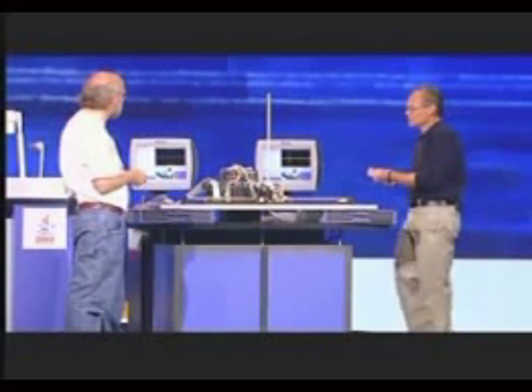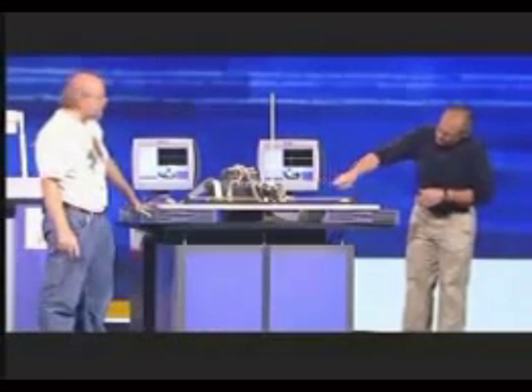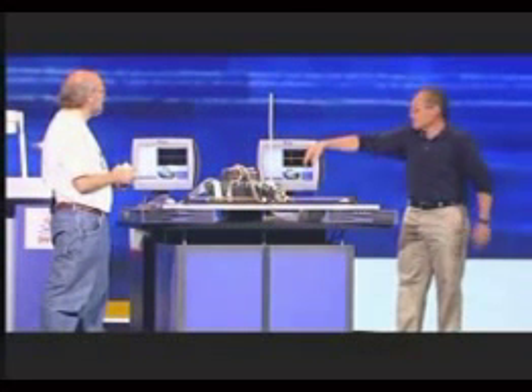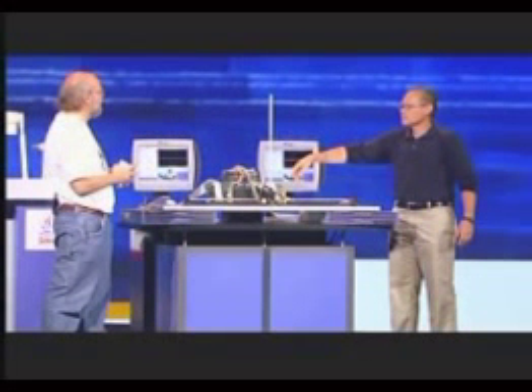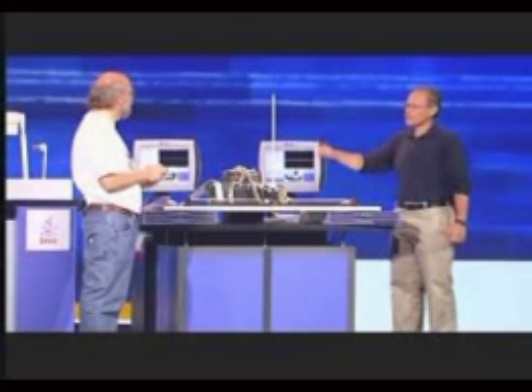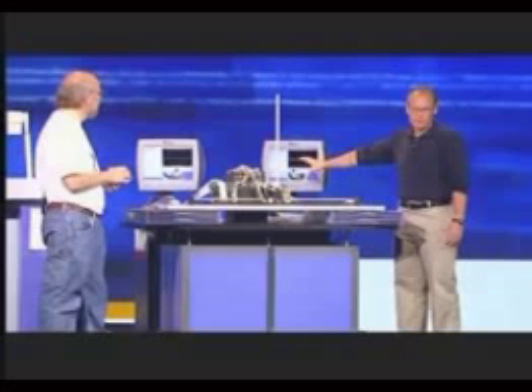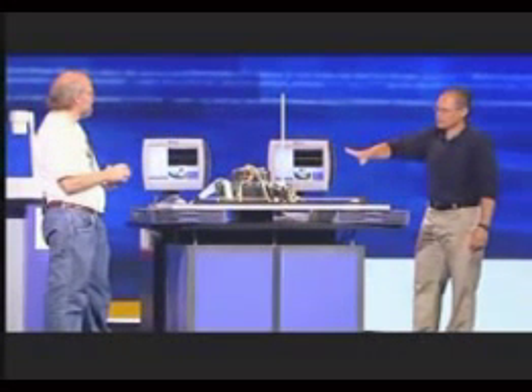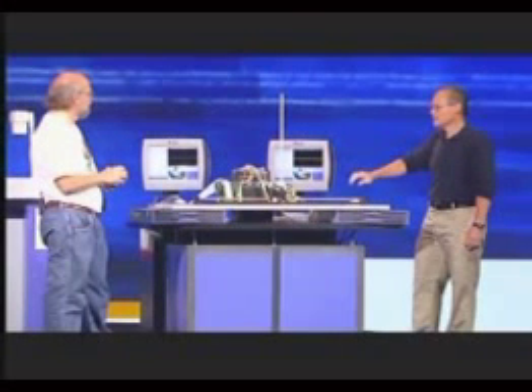The next step is these customers, for these big systems, need fault tolerance. You can't control a 200-ton turbine and wait for the machine to reboot if you have a problem. So you need fault detection and failover, hot backups. You can see there's not just one processor here — there's a second server. The only connection between the two servers is this one little thin wire between the two data acquisition cards. The wire basically says 'I'm alive, are you?' It signals alive when the server is on, the card is powered up, and the application is writing a heartbeat to the driver. So even if the application fails, this line goes low and the secondary takes over. This is all written in Java — application-level fault detection and failover. Except for the wire; we haven't figured out how to do that in Java yet.